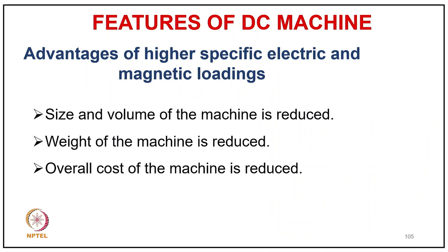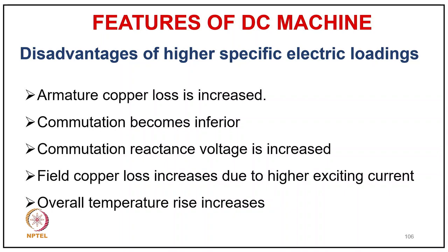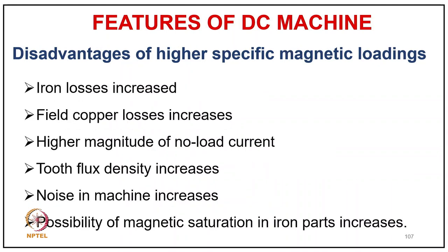Advantages of higher specific magnetic and electric loading: reduced machine size, volume, weight, and overall cost. Disadvantages of higher specific electric loading: increased armature copper losses, inferior commutation, increased commutation reactance voltage, higher field copper loss, and increased temperature rise. Disadvantages of higher specific magnetic loading: increased iron losses, higher field copper losses, higher no-load current, increased tooth flux density, increased noise, and possibility of magnetic saturation.